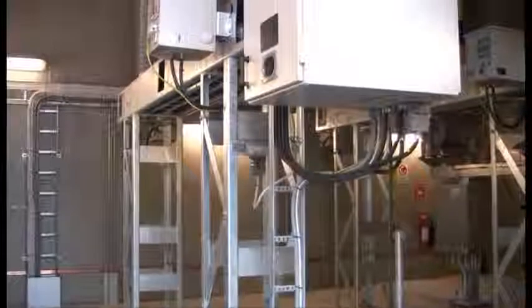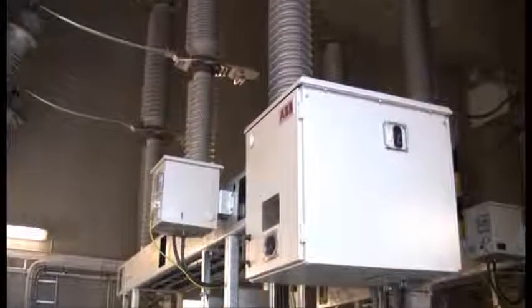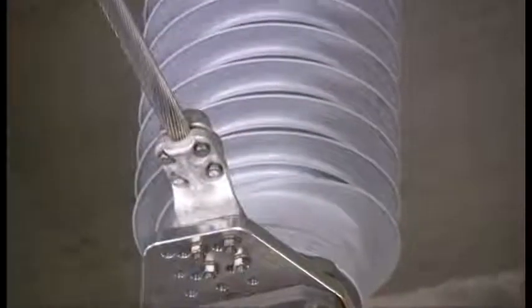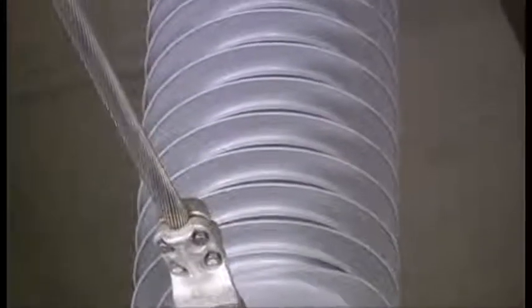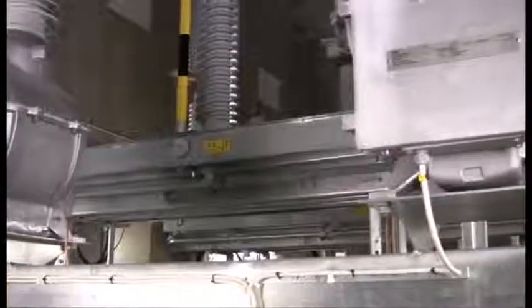The substation is equipped with ABB's disconnecting circuit breakers, which have both breaking and disconnecting functions integrated into the same device. This is a precondition for being able to make the station compact in that separate and space-demanding disconnectors can be eliminated.